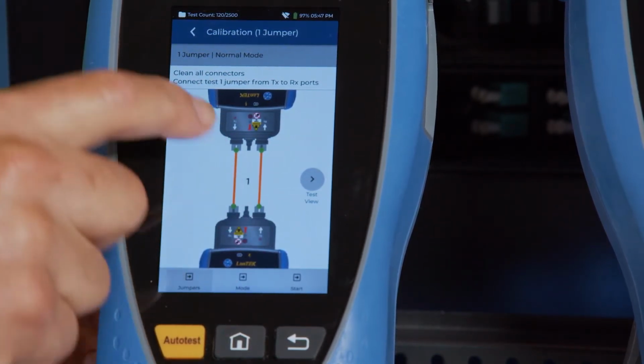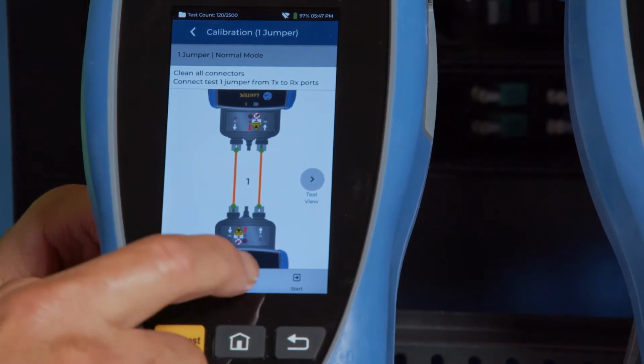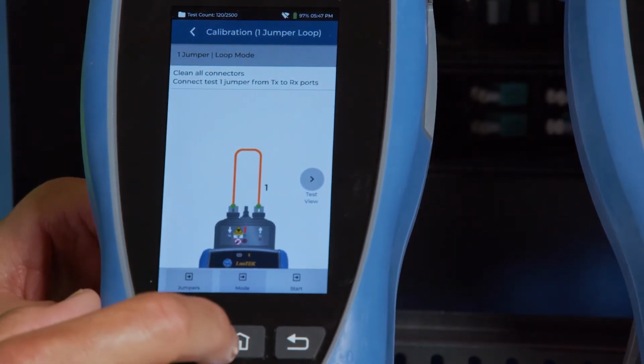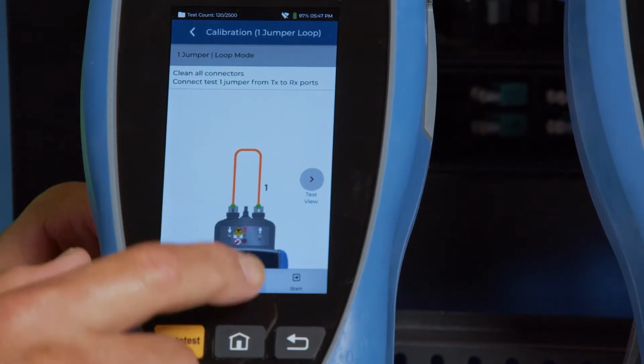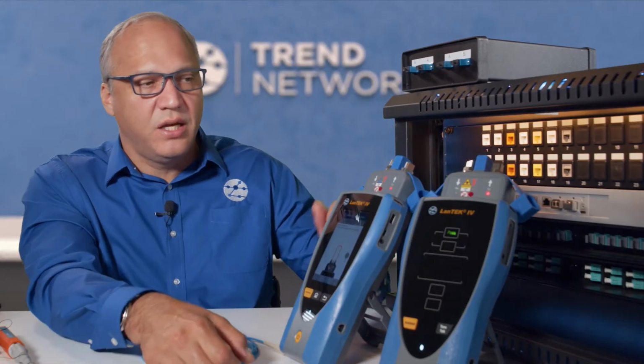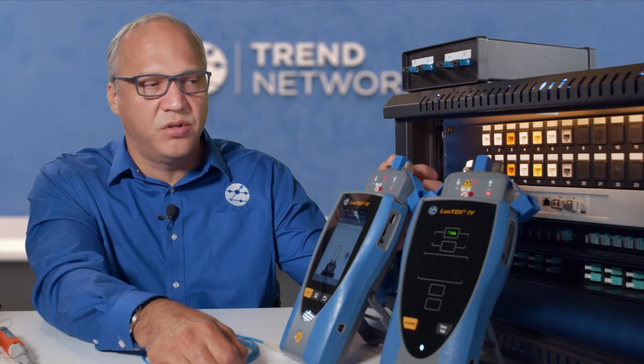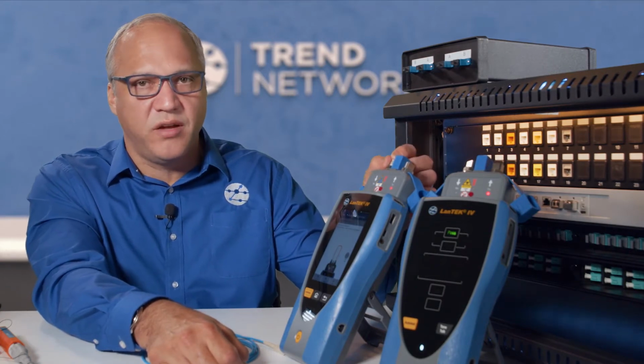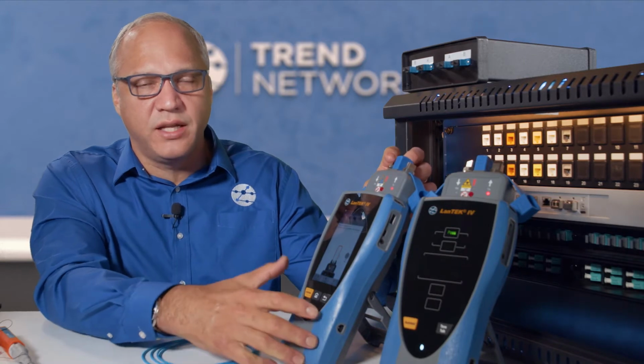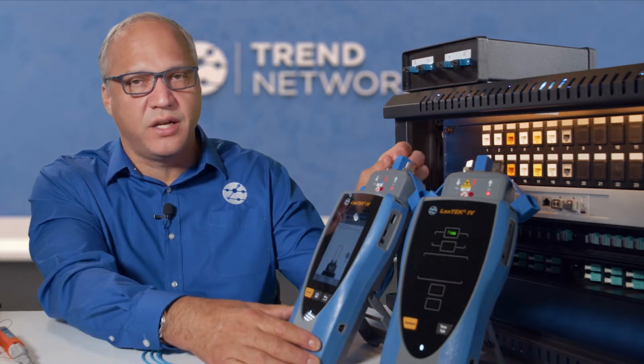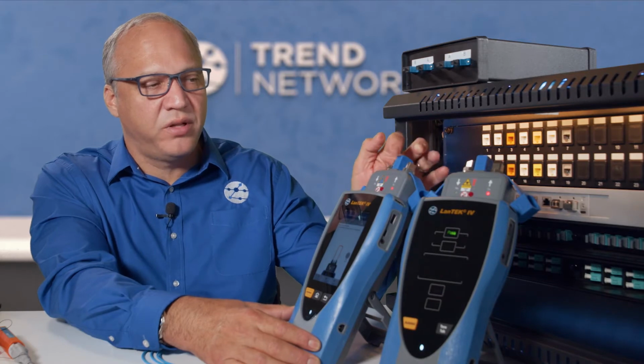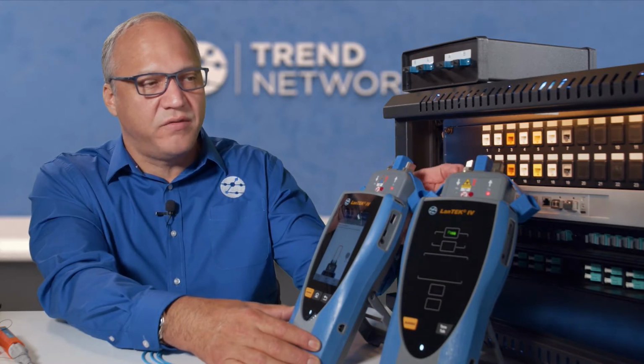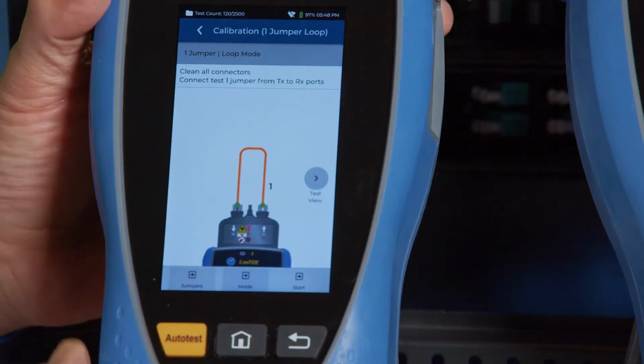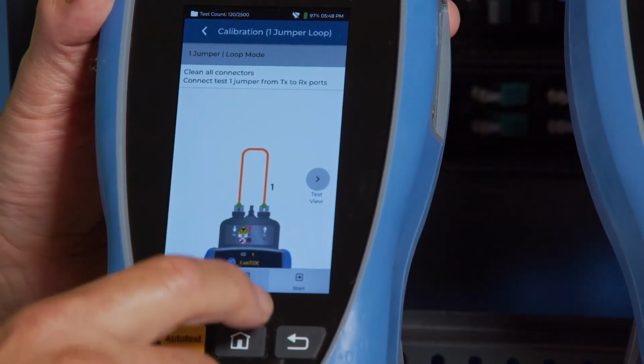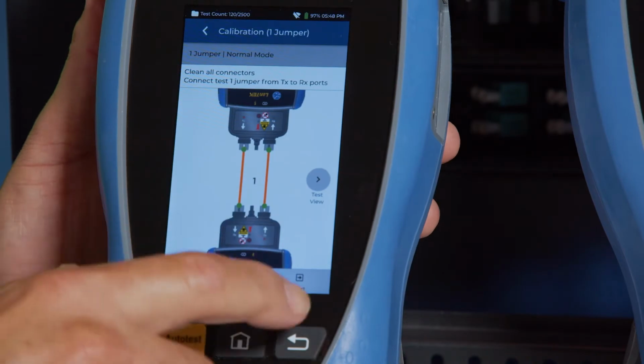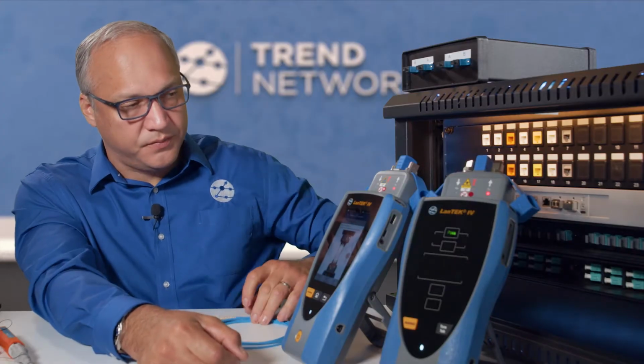The mode will change between the normal mode where we're using 2 handsets and a loopback mode where you're using 1 handset. So the loopback mode is done when you're testing a cable where you have both ends available to the same handset. So an example would be if you're testing a pre-terminated link or a drum of cable that has connectors on it, you can attach both ends to the main handset instead of using both the main and remote handset. So we're gonna go back to 1 jumper standard mode, and we'll go ahead and connect our jumpers.